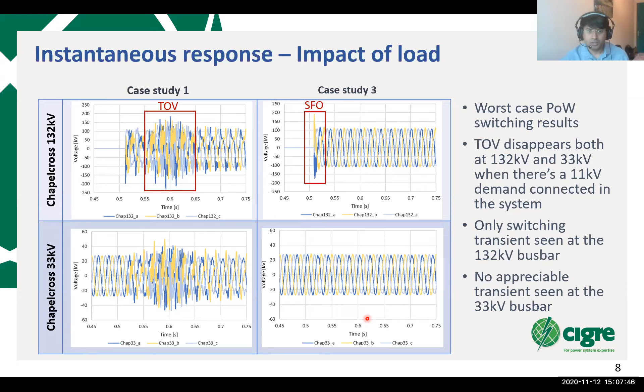Now looking at the impact of saturation on the overvoltage at a particular bus bar. By saturation, what we mean here is that the grid transformer is already energized and the system has reached a steady state before further energizing or closing a breaker, like in this case, the 132 kV unbalanced line. We already know how to interpret these graphs. So the key takeaway would be that when the grid transformer energization is done prior to energizing the transmission line, the influence on the 132 kV and 33 kV overvoltage is not that significant. We have minimal influence on 132 kV, whereas on 33 kV we see a slight increase in the overvoltage, but the proportions as such don't change by much.